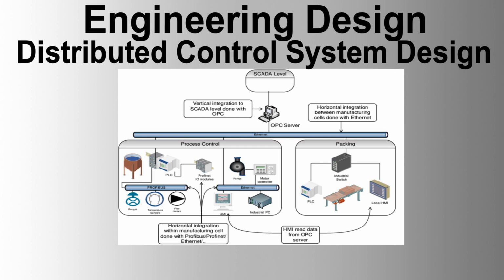Power supplies. 1. General requirements. The DCS must include redundant power supplies to ensure continuous operation in case of a single power supply failure. Each power supply must be capable of supporting the full load of the DCS independently. The power supplies should be sized to handle the maximum load, considering all connected devices and future expansions. 2. UPS system. An uninterruptible power supply, UPS, system must be provided to ensure continuous power supply to the DCS during power interruptions. The UPS system must have a battery backup capable of maintaining power for a specified duration under full load conditions. The UPS must include automatic switchover features to engage battery power without any interruption to the DCS operation.